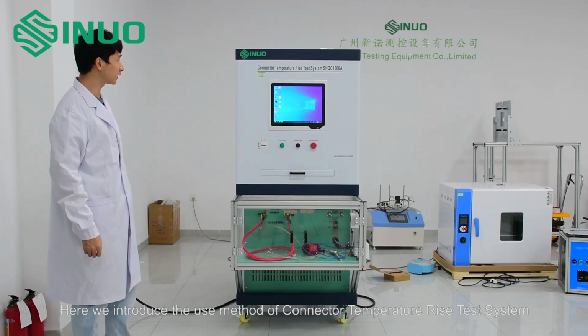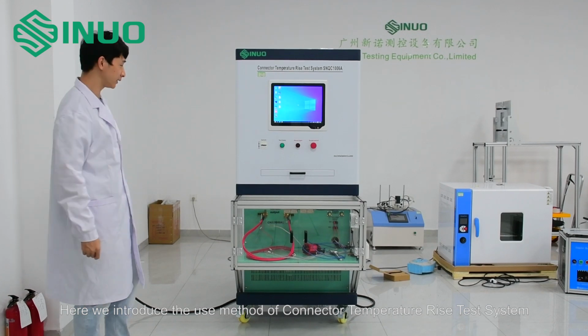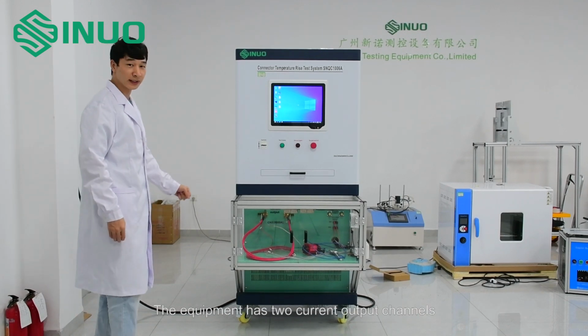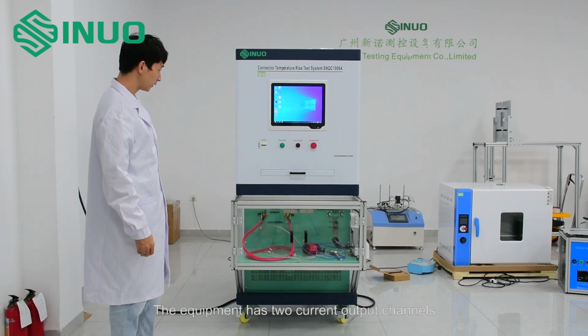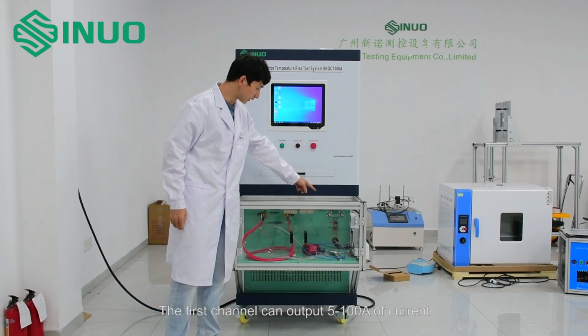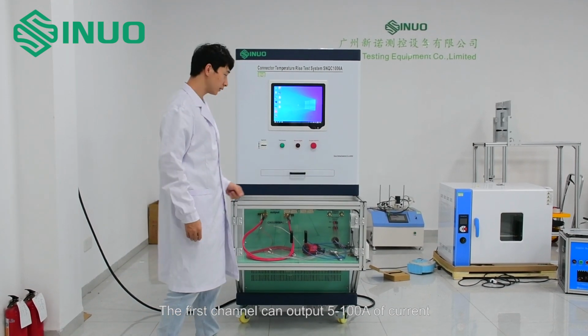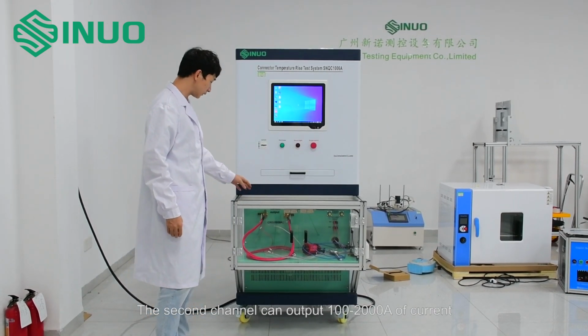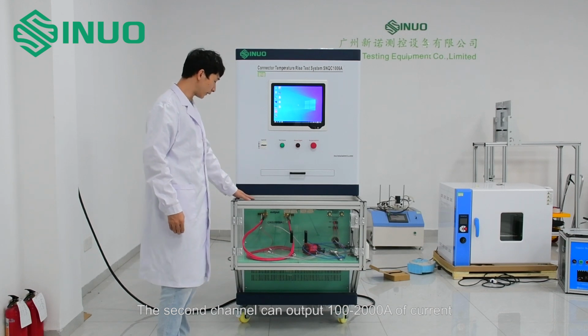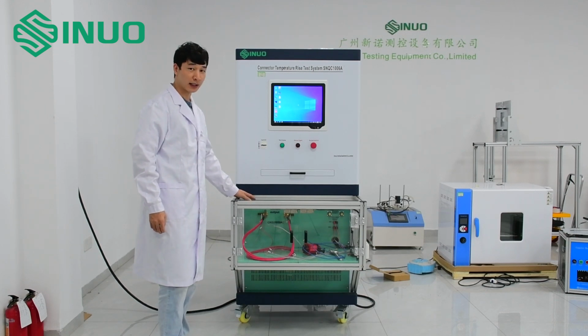Here we introduce the use method of the connector temperature rise test system. The equipment has two current output channels. The first channel can output 5 to 100 A of current. The second channel can output 100 to 2000 A of current.